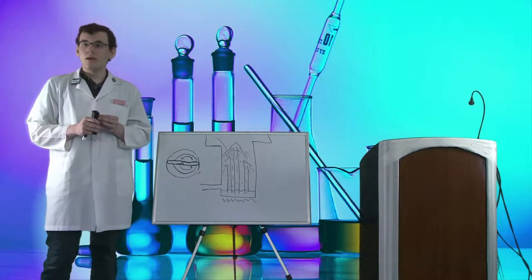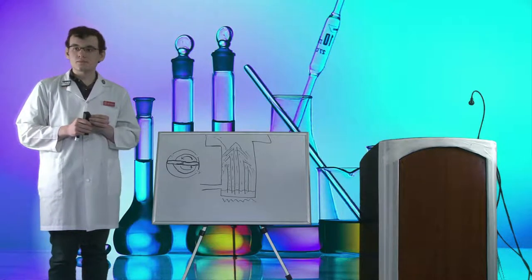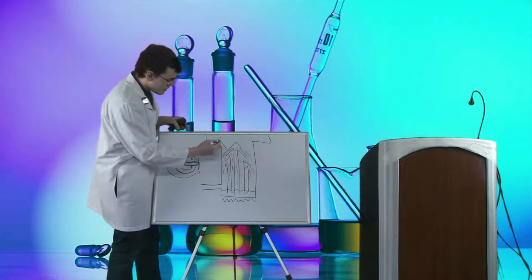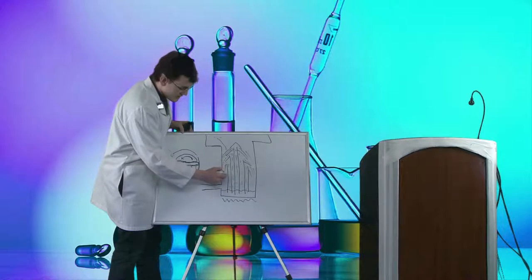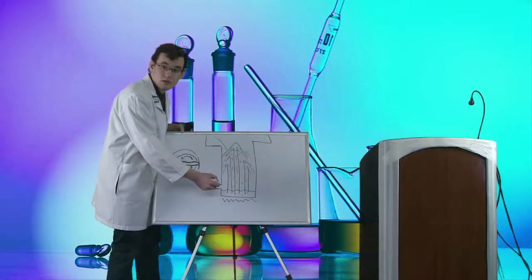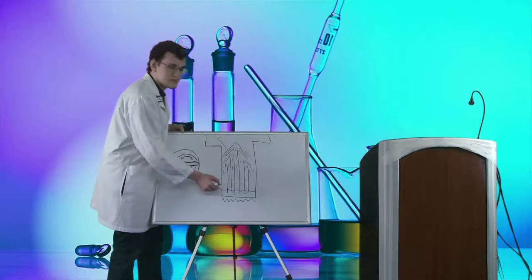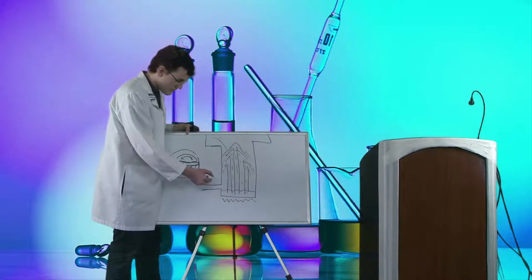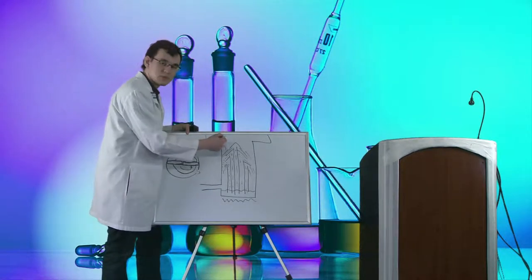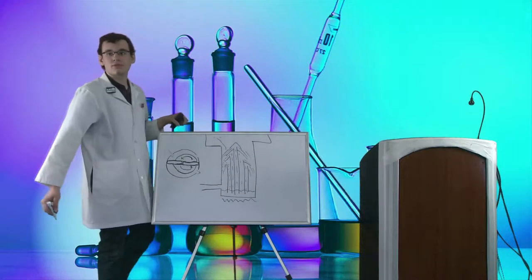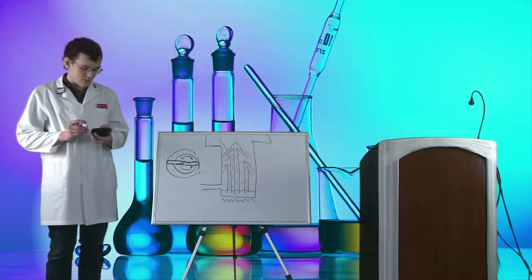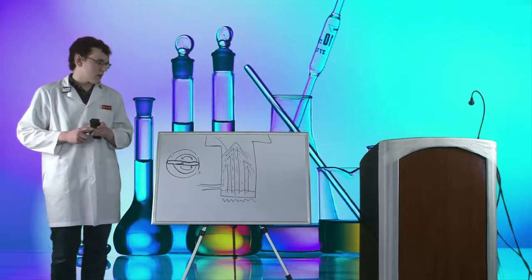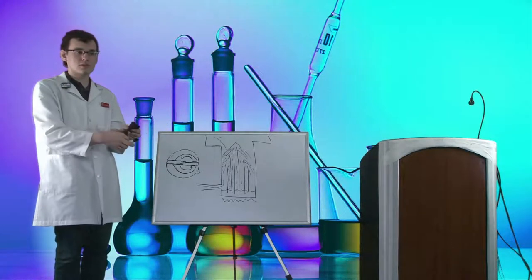Q: Does the heat have to be continuous — if it cools, does air come back out of the oil? The air doesn't get stuck in the oil. What happens is the air molecules get forced gradually down the pump, ending up at a higher concentration at the bottom, and the rotary pump sucks them up from below. If the pump does cool down, the oil stops flowing, and over time, because the base is at a slightly higher pressure, the air molecules will slowly flow back up through it. But air is always being moved out through the rotary pump and exhausted.